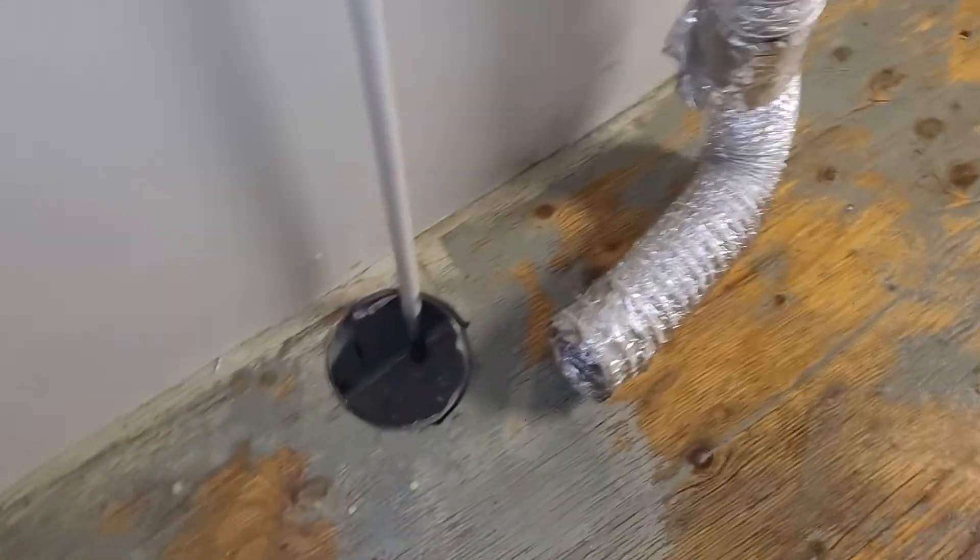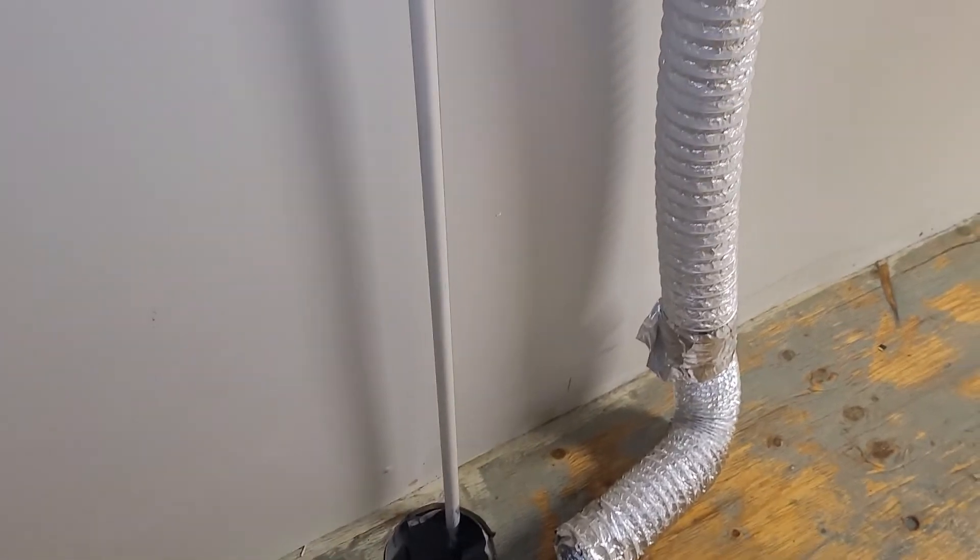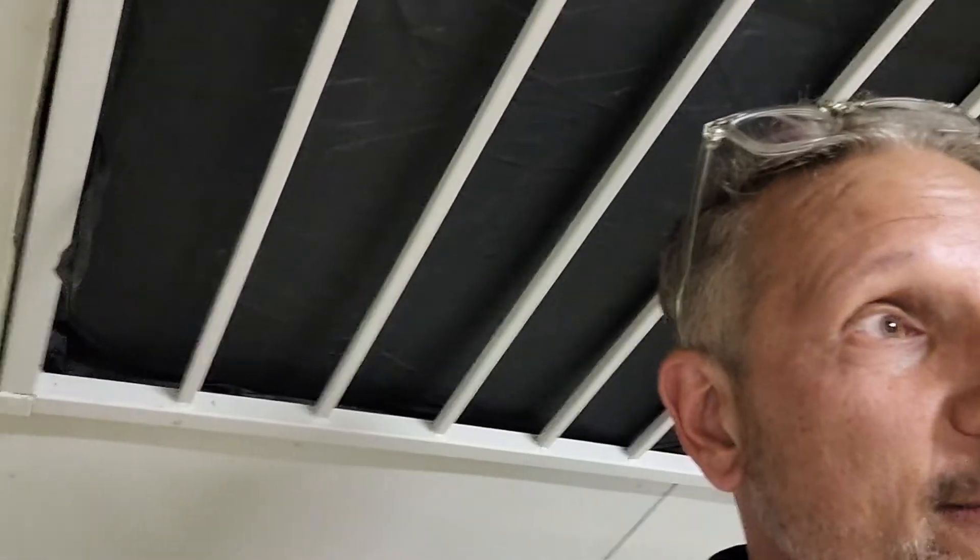Check into a mini-split. What was in here before was a portable unit — you can see this pipe, which ducted air out to the attic. Wouldn't recommend it. Basically you're taking all the hot air and pushing it into the attic, but then the room becomes negatively pressurized and the air comes right back in from the attic. Unless you get a two-pipe unit — but in any case, just get a mini-split.